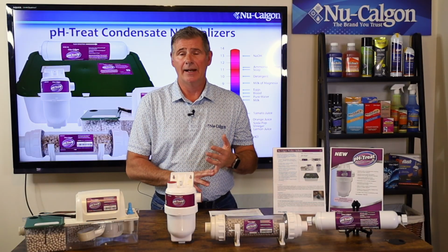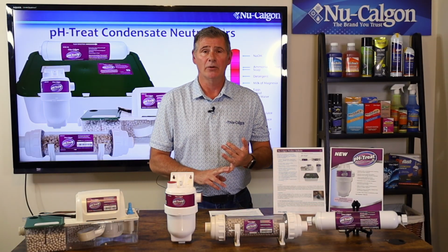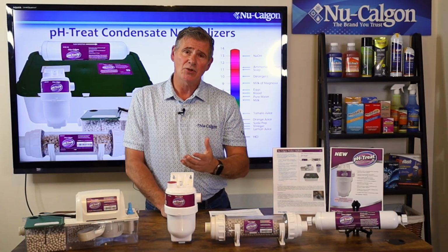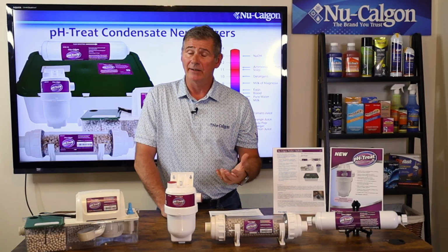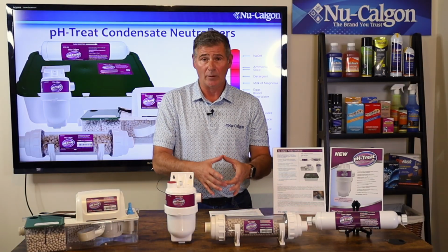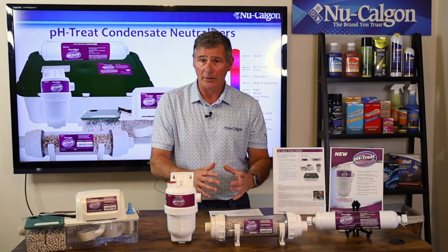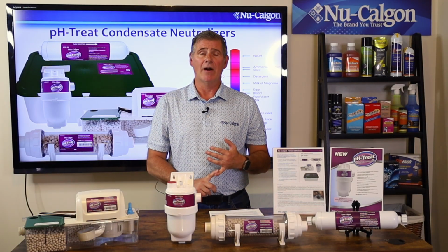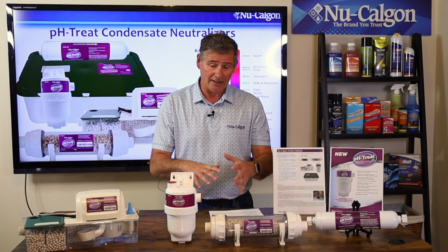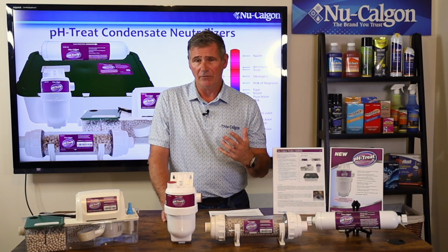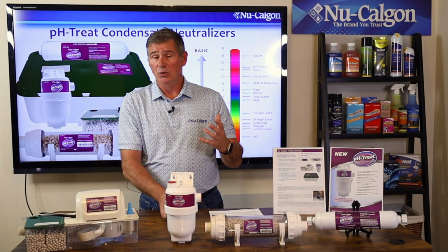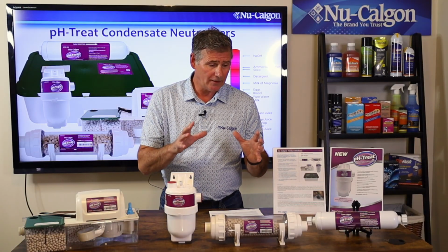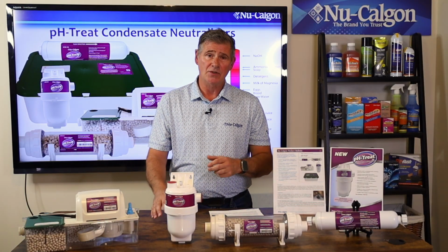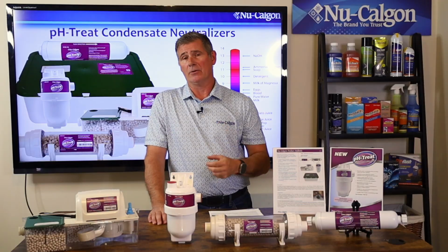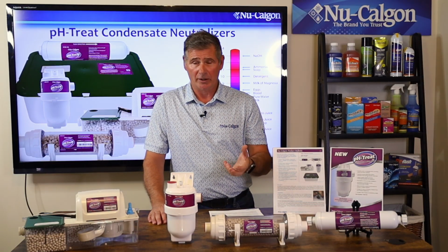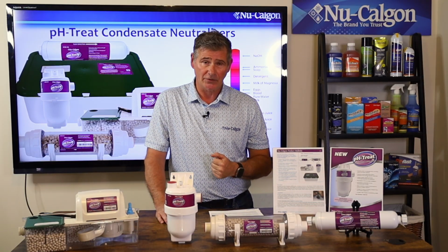That acid can obviously damage the metals in the interior of the equipment itself, but it can also do damage to any drains and drain lines that have any metal in them as well, including the metal grates if it's going right into the ground, and the concrete that's around it. It can also damage the environment, so we've got water table issues. This can get into the drinking water. It can harm vegetation. The other thing is that with sewer systems and septic systems, the acidic drain water from these high efficiency systems can damage the good bacteria in those systems and cause them to stop working, to break down the solids in those systems themselves.